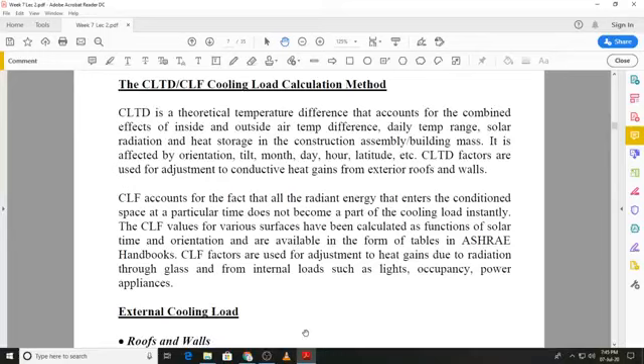The complex mathematics that is required to produce that cooling load temperature difference value is not something we are going to go into. We will simply use the CLTD values that are given to us in the form of tables. And once we have the table in front of us, you will see how we can select the right CLTD value from the table and then proceed with the calculation of the solar heat gain through that surface. So these CLTD values will be used when you are talking about the solar heat gain through exterior surfaces on which direct solar radiation is incident. Those could be walls or those could be roofs.